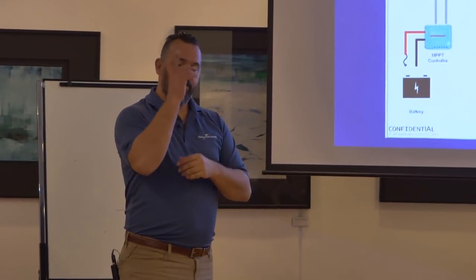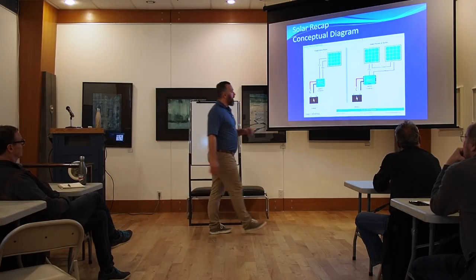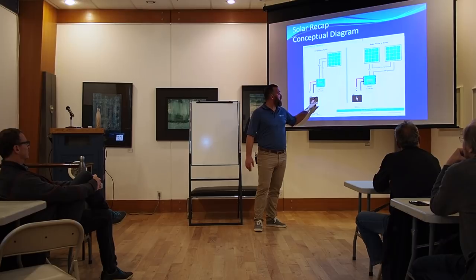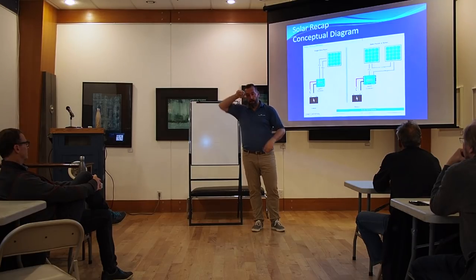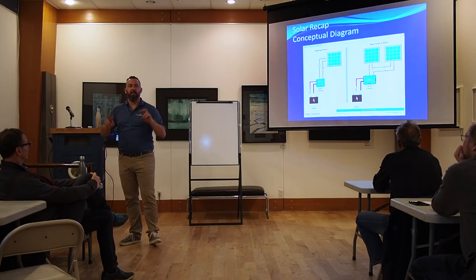Question: why do you need a controller closer to the battery? Some controllers are temperature-compensating with a sensor inside the unit — they want the ambient temperature near the battery. Not all of them. Some have leads that go to the battery for temperature compensation. On my boat, my controllers aren't temperature-compensated, so I have four solar panels coming at the aft of the boat with four controllers literally on the aft bulkhead, aggregated to one pair of cables going to the batteries.